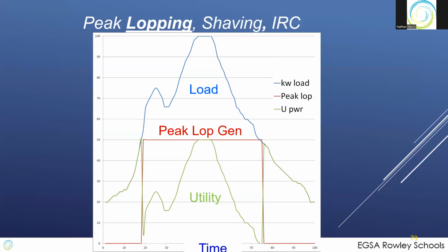So we don't have to know the actual value of watts. We just have to know our load, which is local to the generator in many cases. If the utility tie point's a long way away, we don't have a way to measure that power. We will just take the local load and say, at some value of load, we run our generators. And that's peak lopping. Take the top off. The difference is, of course, your generator runs up to its nameplate value, if you will, and stays there all day and then turns off. So it may not be the most fuel efficient way to do it, but it's one step easier on the control scheme.